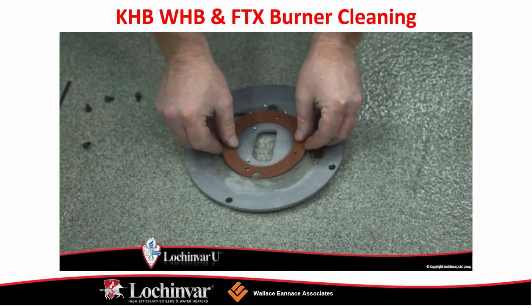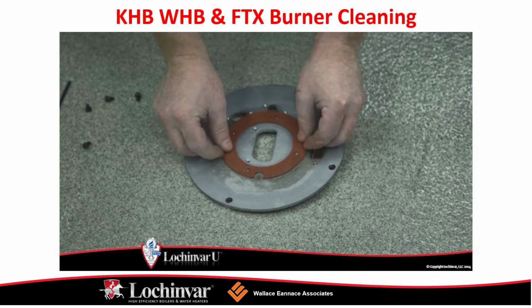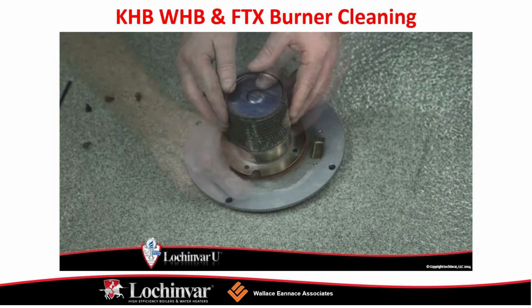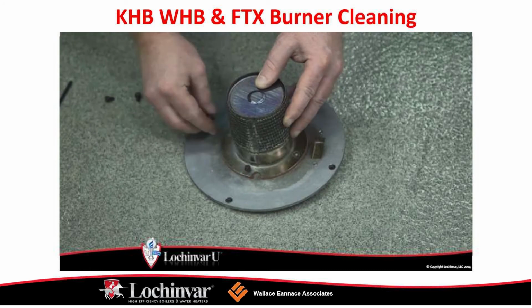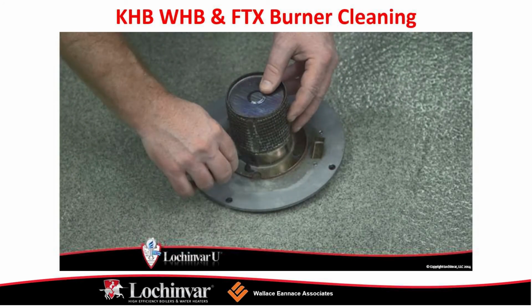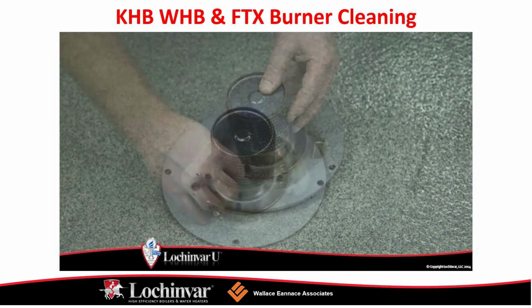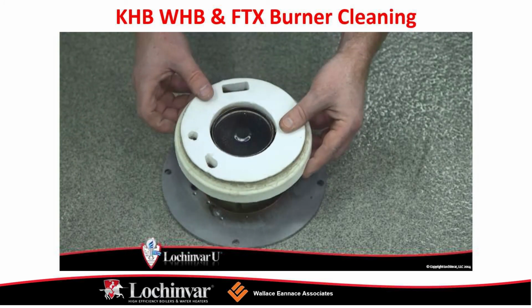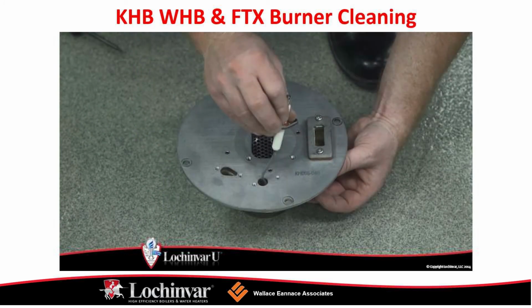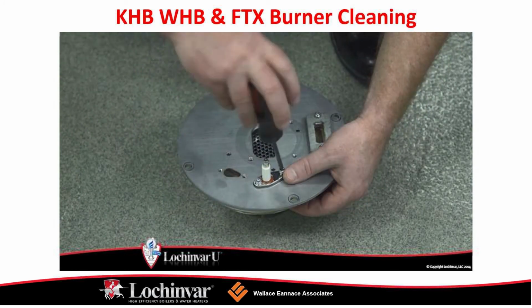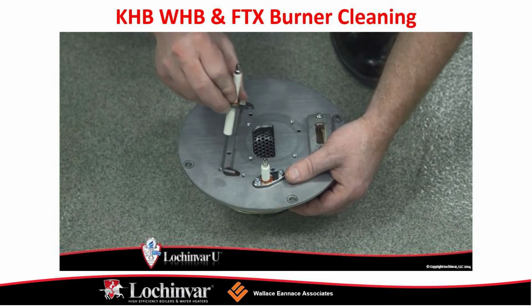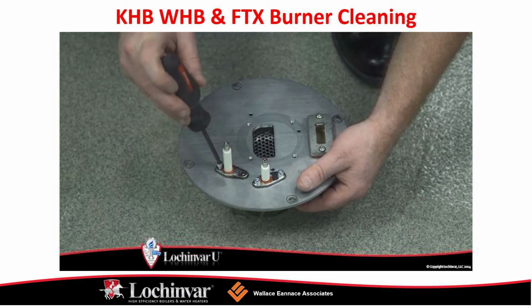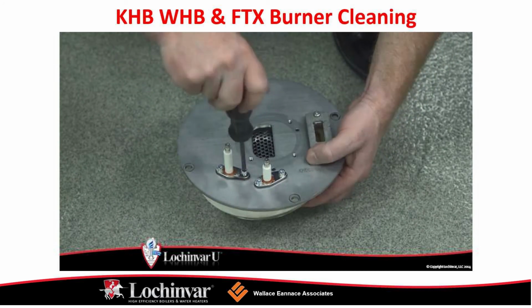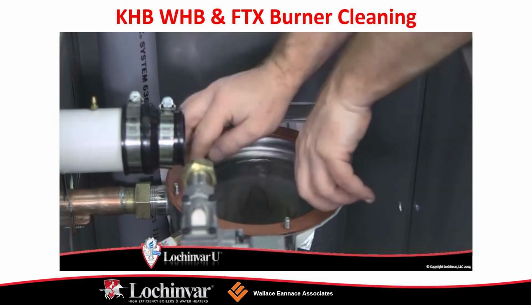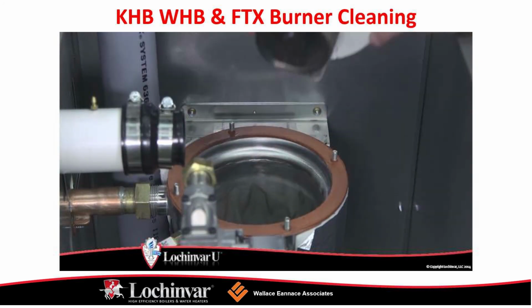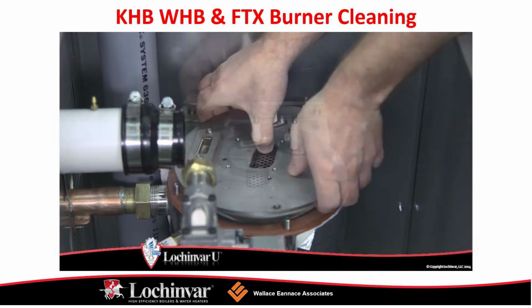Now, using an Allen wrench, remove the screws securing the burner to the heat exchanger door. A gasket is used to seal between the burner and the heat exchanger door. Care must be taken not to tear or damage a gasket. If a gasket is damaged or torn, then it must be replaced. Once removed, inspect the burner for any physical damage. If the burner is damaged, it must be replaced.